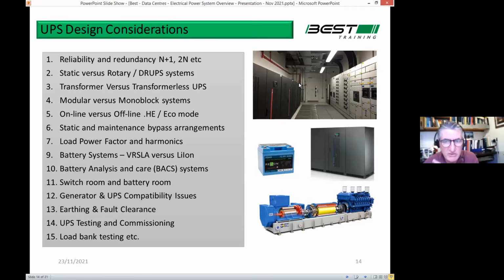So 3 plus 1, one of them would have been a spare. So your capacity is 3 by 400 kVA, which is 1200 kVA. And then you take power factor, everything into account, and it gives you about a megawatt of power. And that's all the switchgear. There's quite a lot of switchgear goes into just feeding those 4 modules, taking the power back off them, and then sending the power out to the servers. And that's the next part of our journey we're going to look at.